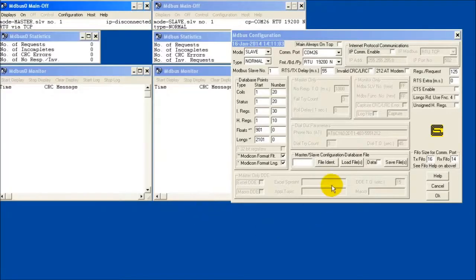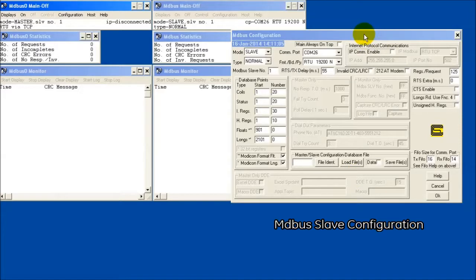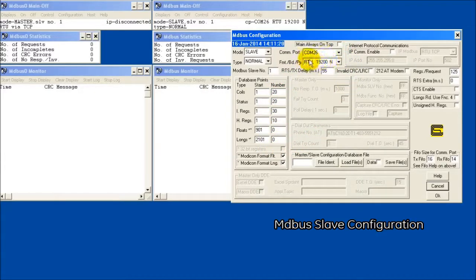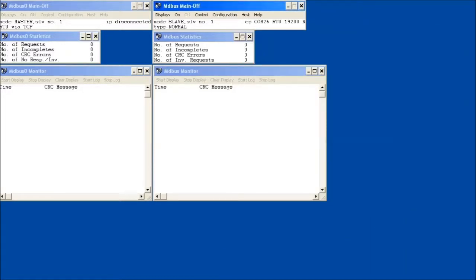I will enable a slave device on COM2 of the remote radio. This simulates the RTU or PLC device that would be connected in field installations. I will configure the MDBus slave to respond with the same register data the access point is requesting. I will ensure the baud rate and parity are consistent with the settings on the remote radio's COM2 port.